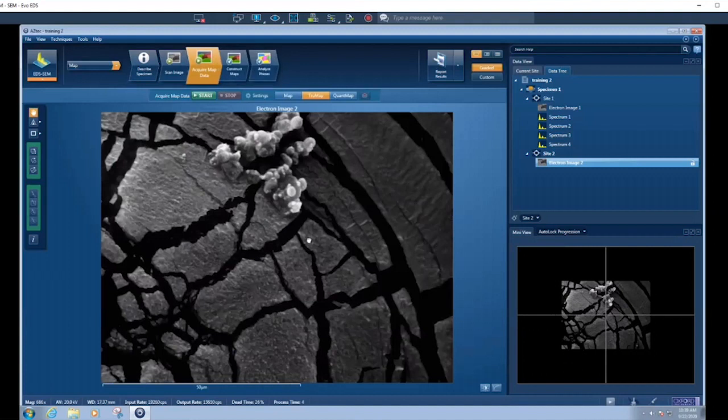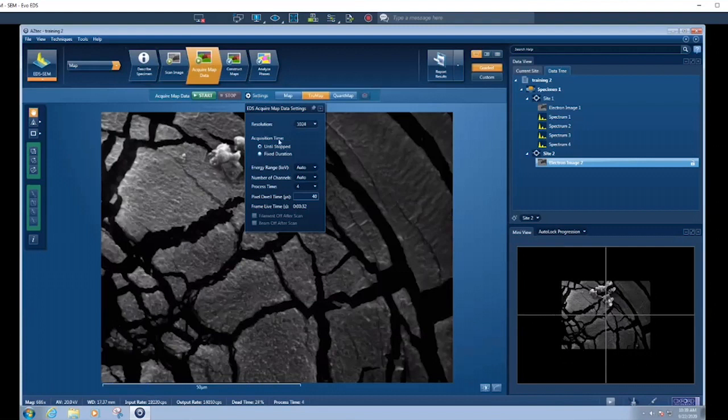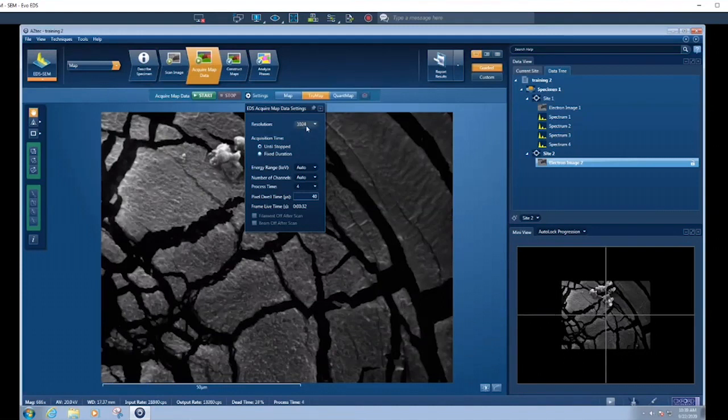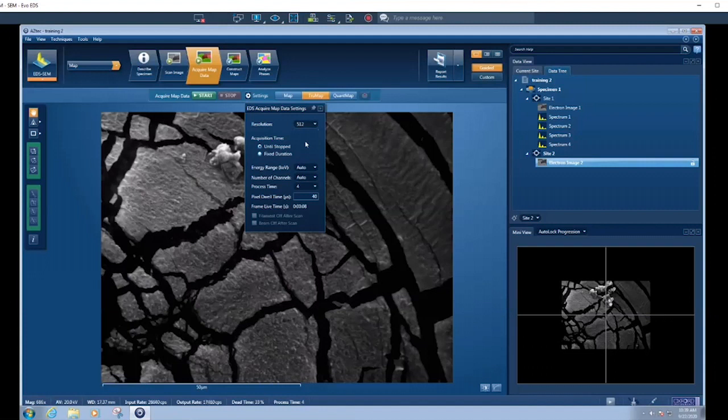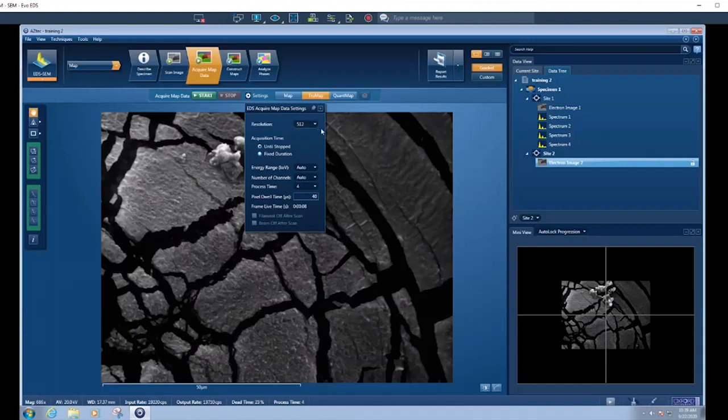As for the acquire map settings, we've moved across to one more step. We go to settings, we choose the resolution of the map. There's no point doing a resolution that's higher than the image we've taken, so you should always do an EDS map that's the same or less. I'm going to go with lower because this is the thing of, do you need more spatial information or do you need more signal? If you want to count for the same amount of time but you want to have more signal per pixel, then it's best to have less pixels because then it can collect that signal more per pixel.